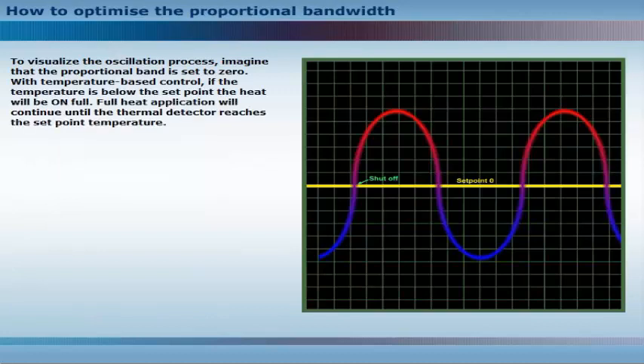To visualize the oscillation process, imagine that the proportional band is set to zero. With temperature-based control, if the temperature is below the set point, the heat will be on full. Full heat application will continue until the thermal detector reaches the set point temperature.